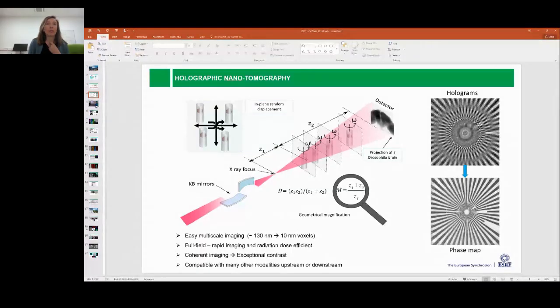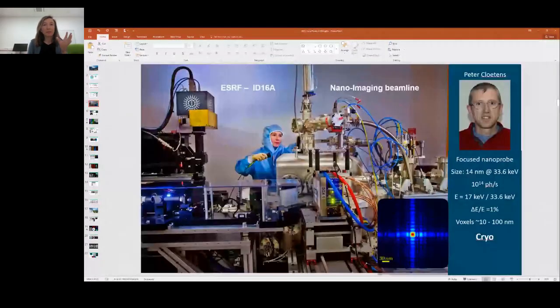This is just a picture of the instrument. So inside here, we have combined the X-ray holography, the X-ray fluorescence, and there's also a visible light inline microscope. So basically the sample can be either at room temperature or vitrified, and is placed in this chamber on a rotational sample stage, and then it can be imaged with both the technologies that I mentioned.